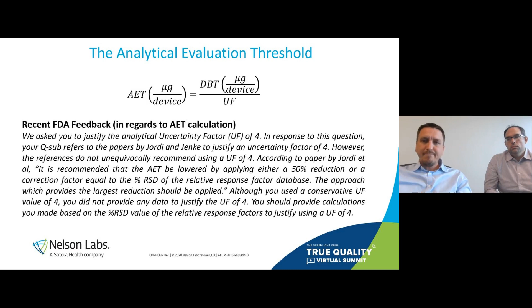There's a formula for describing this inside a report. I've seen the FDA ask for this formula specifically. You can see the FDA feedback there where they want to know what dose-based threshold did you use, and also what type of uncertainty factor was used in extending that dose-based threshold over to an AET.